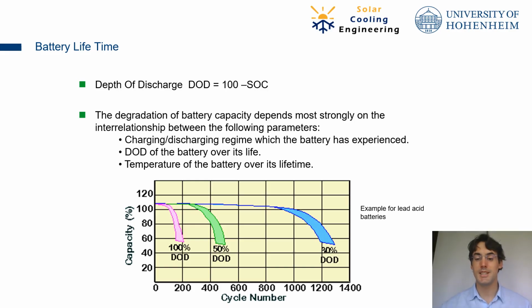Or perhaps you have 50%, so you go from 100 to 50, or from 90 to 40, or 30%, going from 100 to 70, for example. Depending on how much or how little you discharge your battery per cycle, the longer the lifetime of the battery will be, and this is determined by the cycle number. So if we discharge only 30% of the battery every day, we can have 1,200 cycles, which is around 4 years. And if we discharge the battery 100% per cycle, it won't last even 1 year.